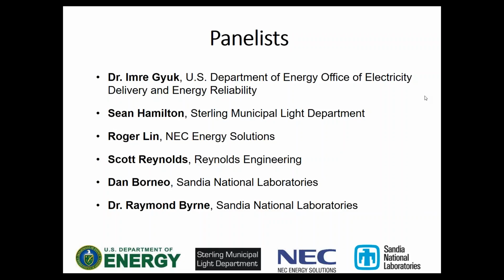For instance, if you're trying to provide a peak load reduction and the requirement is 3 megawatt-hours, that might constitute your end-of-life condition. So you might size it to be 3.9 megawatt-hours up front so it provides at least 3 megawatt-hours through a 10-year service life.